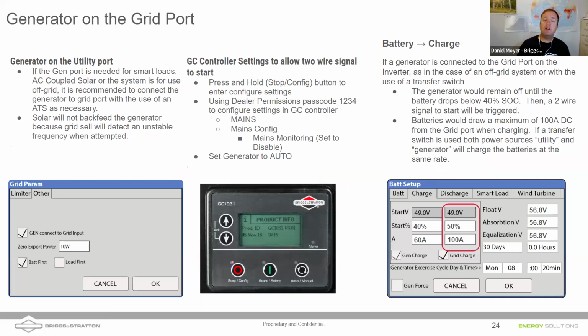So we're looking at a little bit of the programming. Now we're still bringing the generator in on the grid port. Sorry. So again, this is one of the things that Nathan had mentioned earlier. If we are going to bring a gen onto the grid input, we need to be able to check that as well. One thing we already covered in the center was programming the generator so that even if it still sees the presence of grid, because it's being fed by the backed up loads out of a Sol-Ark, it will go ahead and still start as well. And then we also, again, Daniel, covered...